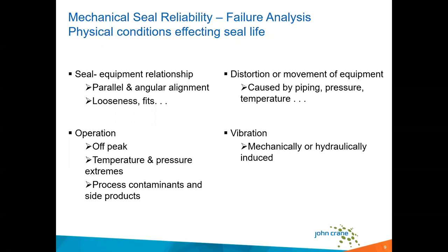It gives you a little checklist for evaluating mechanical seal failure when you start undergoing any troubleshooting efforts. It's good to consider one, if not all, of these physical conditions that impact the performance of the seal. In my experience, no matter how elaborate the seal design, internal misalignment between the seal and equipment often contributes to a lot of these issues.